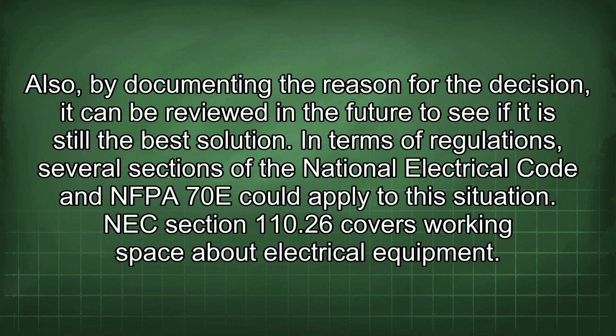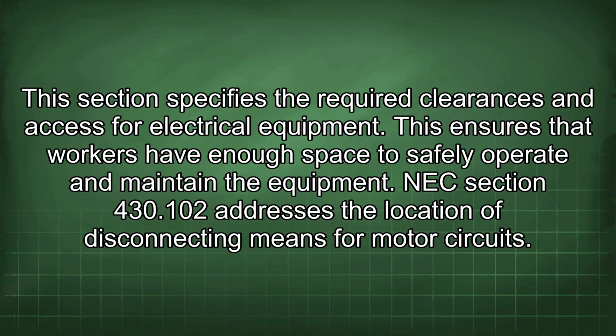In terms of regulations, several sections of the National Electrical Code and NFPA 70E could apply to this situation. NEC Section 110.26 covers working space about electrical equipment. This section specifies the required clearances and access for electrical equipment. This ensures that workers have enough space to safely operate and maintain the equipment. NEC Section 430.102 addresses the location of disconnecting means for motor circuits.